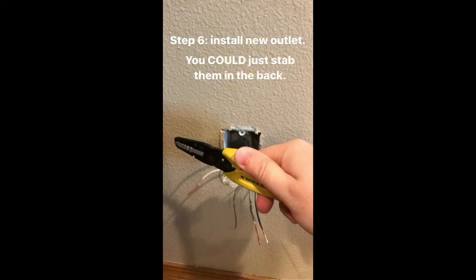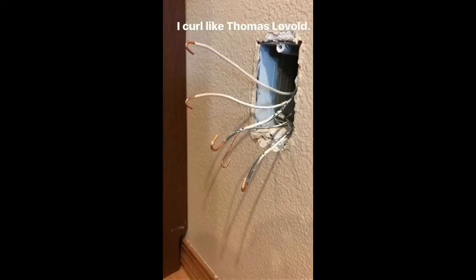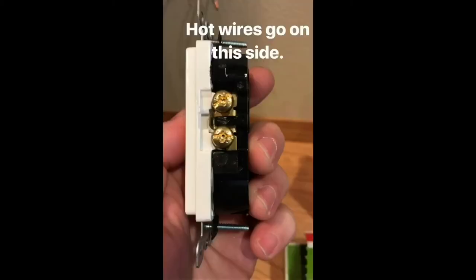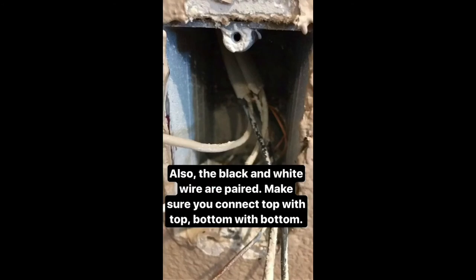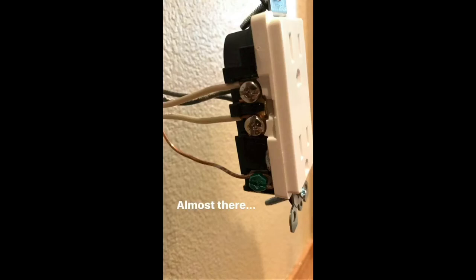Step six: install the new outlet. You could just stab it in the back — it would be faster, but faster doesn't always mean better. So I curl the wire like Thomas Lovold — a curler from Norway. The hot wires go on this side, white wires go over here, and your copper wire goes down here. Also, the black and white wires are paired — make sure you've got top with top, bottom with bottom. It also helps to curl the wire with the tightening of the side screws.